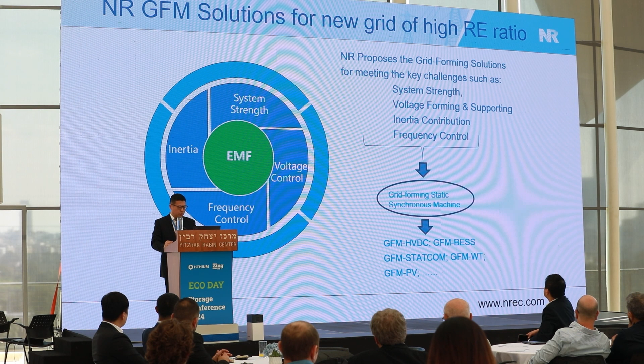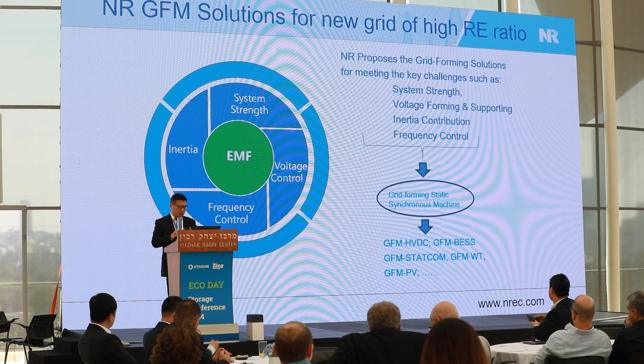So based on all this analysis, we developed the grid forming solution for the new generation of high penetration renewables. It's not only for battery storage. The grid forming solution can meet key challenges such as system strength, voltage forming, inertial contribution, and frequency control. So we can provide grid forming for battery storage, HVDC, STATCOM, and PV, using grid forming technology to support this high penetration renewable grid system.